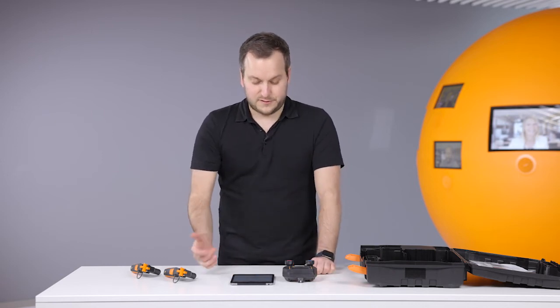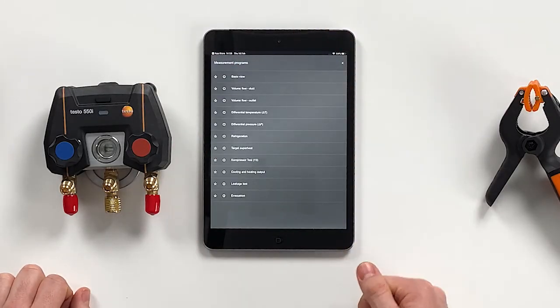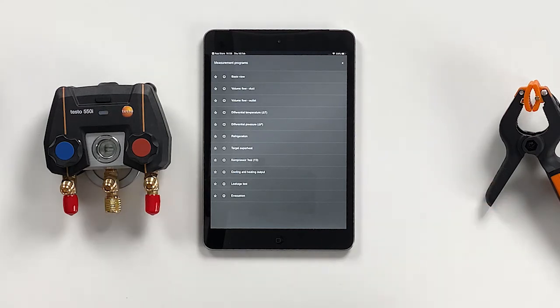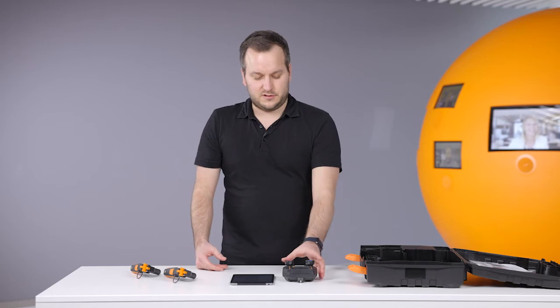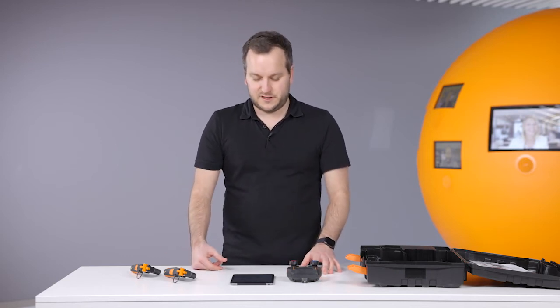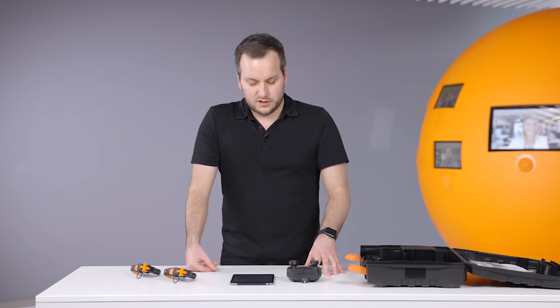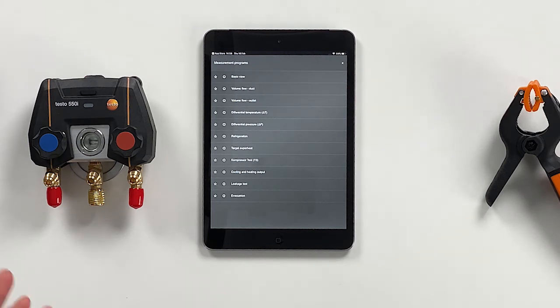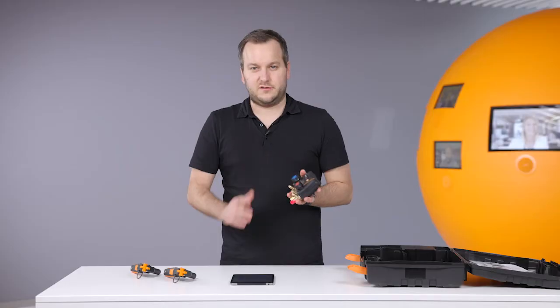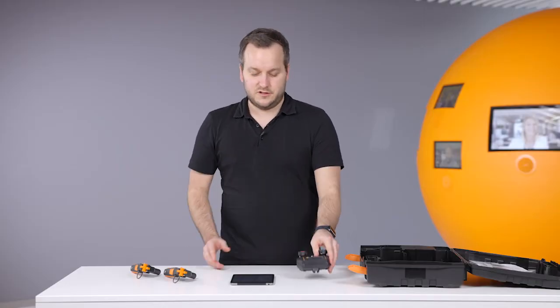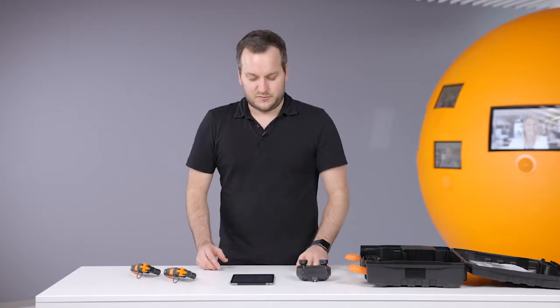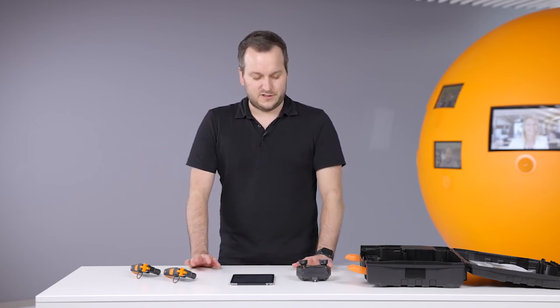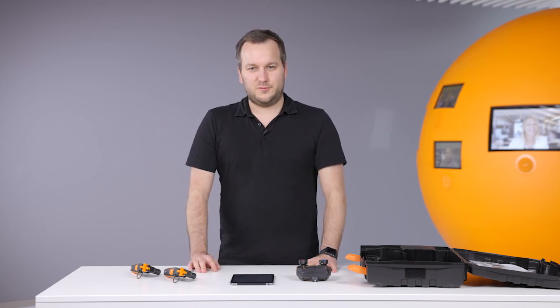Moreover, there are in the app a lot of additional applications where you can use smart probes. For example, you can add to this setup two 605i probes for doing target superheat measurement, or you can add volume flow smart probes to do a volume flow measurement. Everything is possible within this app, and this always at a long range. The 550i, for example, has a range of over 150 meter Bluetooth connection. This is how you can work smart, and this is why we have done the Testo 550i. I hope you will enjoy working with it.